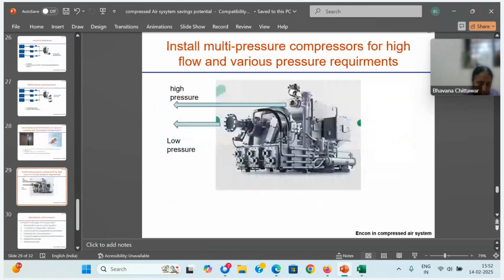Then there are a lot of clients who use multiple pressures. Some applications require 3 bar, some require 4 bar, for process-linked clients like paper plants. There are compressors available which give multiple air pressures, like centrifugal compressors. From one stage you can take low pressure, 2 bar or 3 bar. At another stage you can take high pressure, 5 bar. You have to indicate your requirement to the OEMs, and they can supply. This will work as the most energy efficient method.